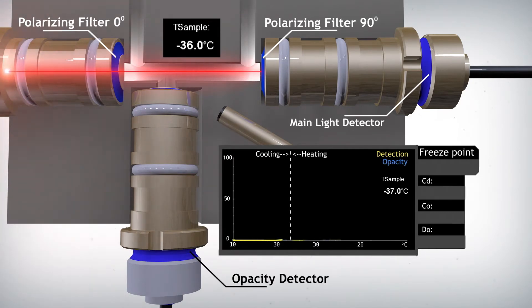Note that the light beam passes through and is polarized by the first polarization filter, but is blocked by the polarization filter configured perpendicularly to the main light detector. As the sample approaches close to minus 38 degrees Celsius, fine crystals start to appear.